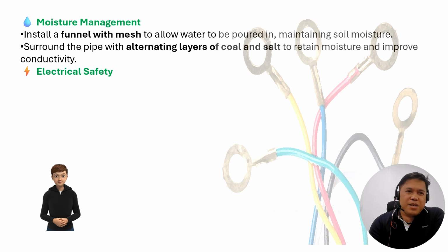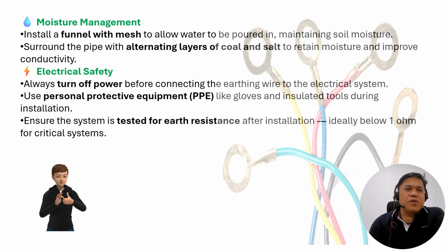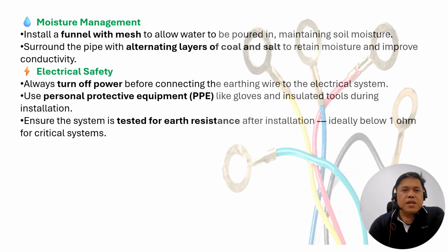So electrical safety - what is the electrical safety? Always turn off power before connecting to the earthing wire electrical system, and use personal protective equipment. Ensure the system is tested for earth resistance after installation, ideally below 1 ohm for critical systems.